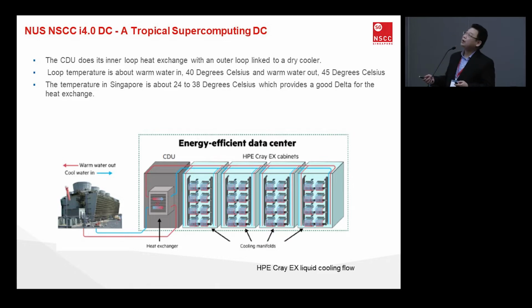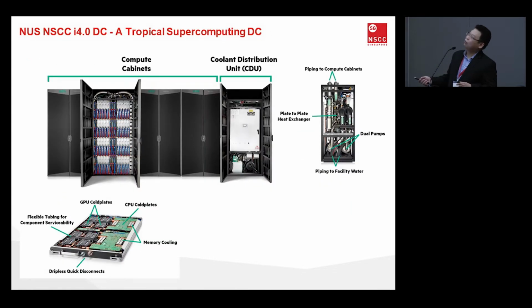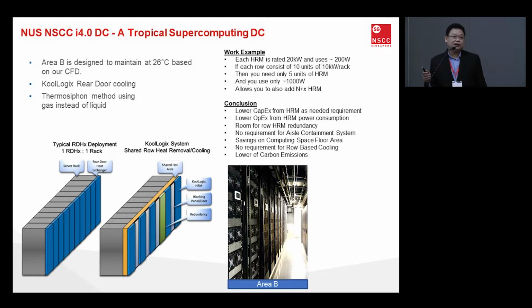All right, so there's a bit of an inside look at what the Cray looks like, and of course the CDU unit, the inside where it does the heat exchange, and how one of the nodes looks like. Now let's talk about area B. Area B is the same thing, it has no aircon. Surprisingly, we can get rid of CRAC units. The only aircon there is an FCU, to provide positive pressure to the room, to keep dust from coming in the moment you open the door.